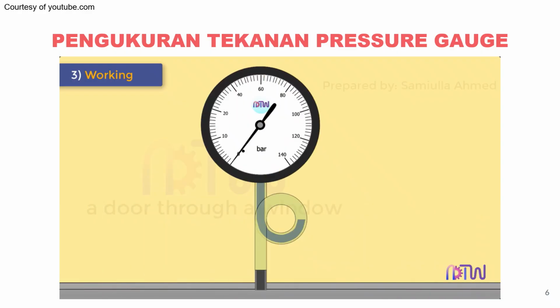In real-life application, the pressure gauges are mounted with siphon tube. Siphon tube is a simple device used to protect a pressure sensor from high-temperature media, such as steam. It can also be used to reduce the potentially damaging effects of rapid pressure changes. When first installed, the siphon should be filled with water or some other suitable separating medium. This medium continuously remains in contact with the Bourdon tube.